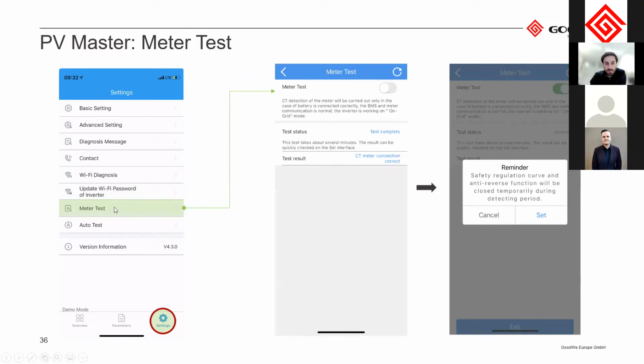The next option in the menu is the meter test. This is usually already done when you've entered the basic settings, but if you change some things with the CTs afterwards and want to run only the meter test without going through everything again, you have the option here. Just enter here, check this, and it runs a test to check if the CTs are correctly installed.